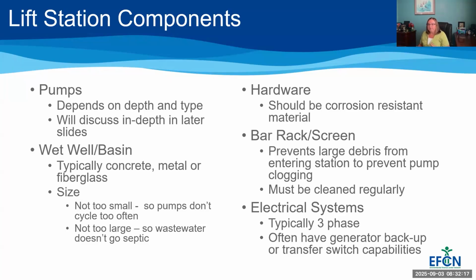And then the last component on this slide is your electrical system. Of course, pumps have to have some type of energy to run, and typically it's electricity. Sometimes we might have different types, it might be a generator, but it's usually coming from your electrical grid. And the pumps in lift stations, again, are typically 3-phase pumps. Sometimes they're single phase, if they're super small, or if you don't have reliable 3-phase power in the area where the lift station is. And I'm not going to go into great detail about electricity and the differences between single phase and 3-phase, but it's a difference in your voltage.